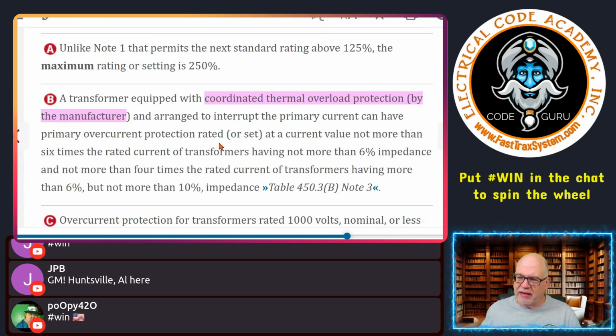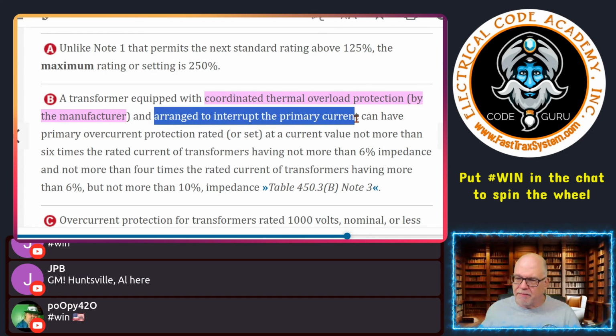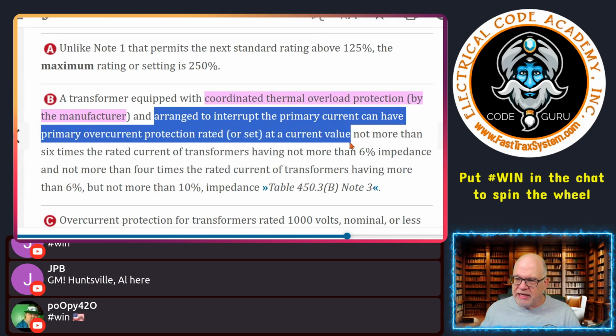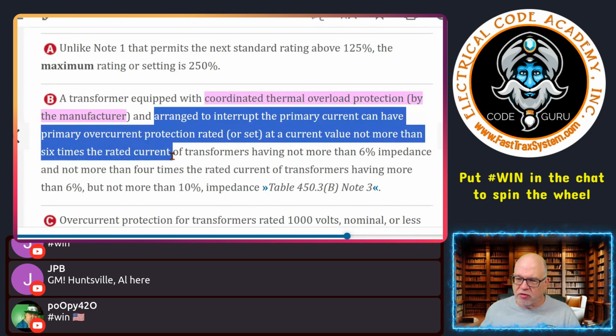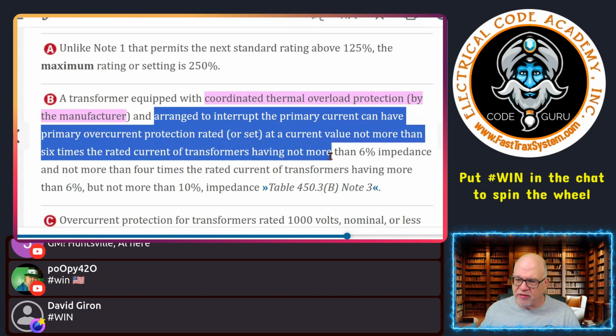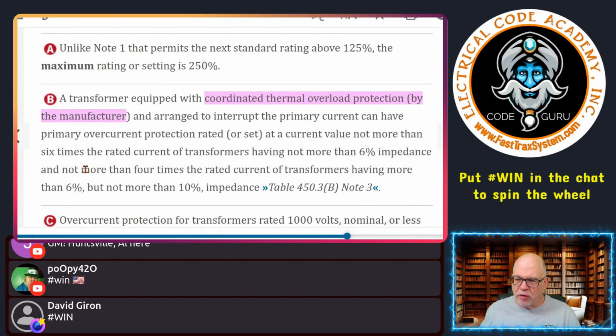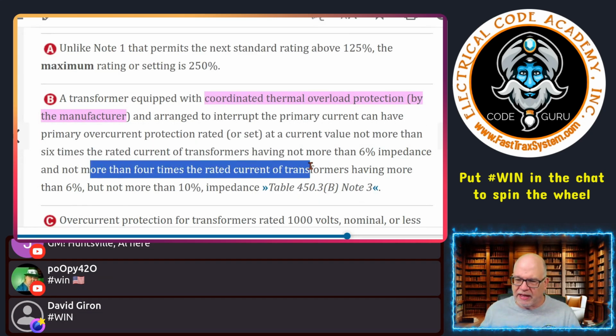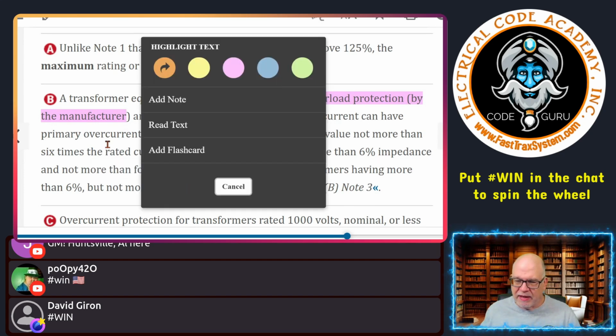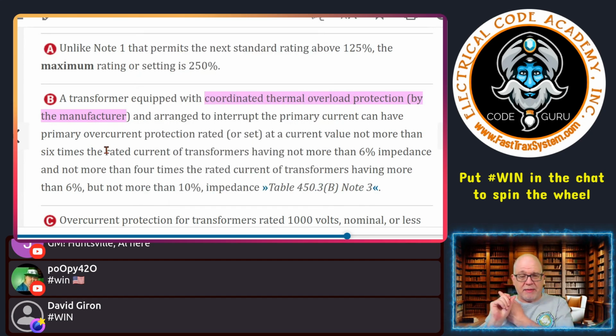And as we said here, and it's arranged to interrupt the primary current, it can have primary overcurrent protection rated or set at a value not more than 6 times the current rating of the transformer, having not more than 6% impedance, as we saw, and not more than 4 times the rated current of a transformer that has more than 6%, but not more than 10%, impedance. So that's why you need to know what the nameplate is.